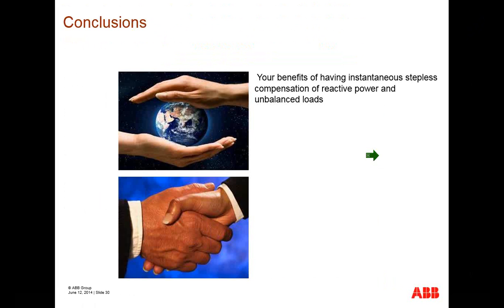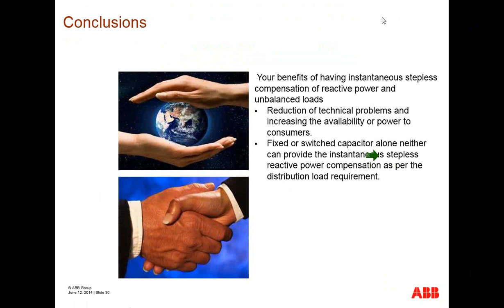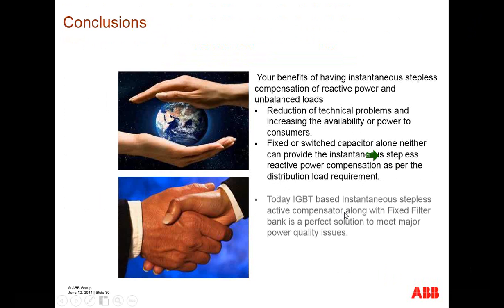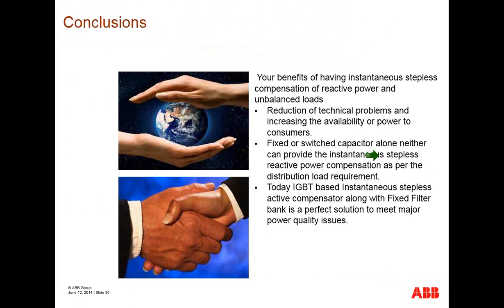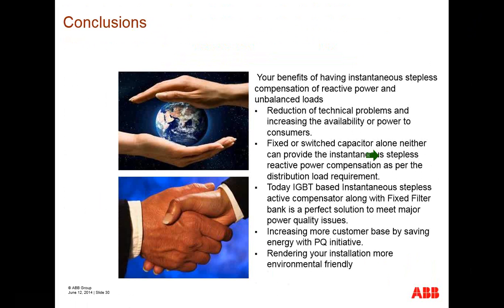So in conclusion, the problem which we are facing day to day is increasing the availability of power consumption. Fixed and switched capacitors alone cannot provide the instantaneous stepless reactive power compensation as well as the distribution load requirement. Today, an IGBT based instantaneous active compensator along with fixed compensation or filter bank can be a perfect solution for improving power quality and increasing the customer base, because of the energy saving we are able to give support to our other consumers as well, and the installation is more environmentally friendly.